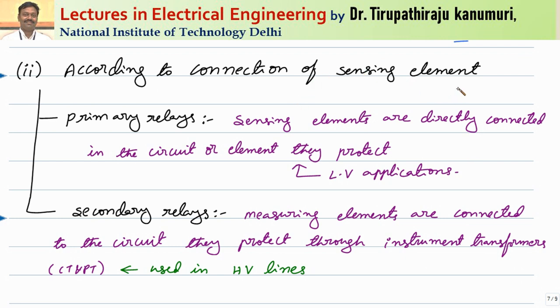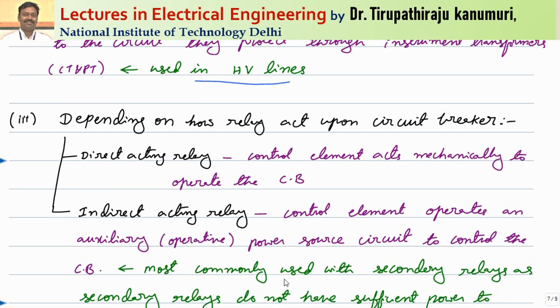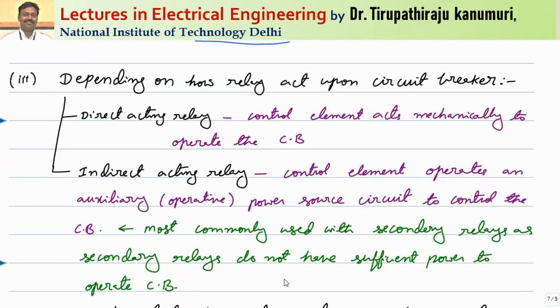Now, according to the connection of the sensing element, there are two types: primary relay or secondary relay. In a primary relay, the sensing element is directly connected to the element being protected — used in low voltage applications where the relay can be connected directly to the supply. In a secondary relay, it is connected through instrument transformers, used for high voltage applications to provide isolation and reduce current magnitude.